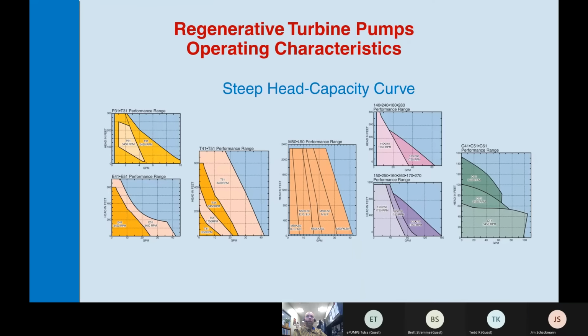Moving along, a little bit about the characteristics of a regen turbine. The main characteristic of a regen turbine is that it is a high head with low to moderate flows, where you're probably used to a centrifugal pump, which is the most common pump in the world, where it's a higher flow with a lower head or pressure. And with a centrifugal pump, the higher the flow, the more horsepower that is needed. It's exactly the opposite with a regen turbine pump, where the higher the pressure, the higher the horsepower is needed.